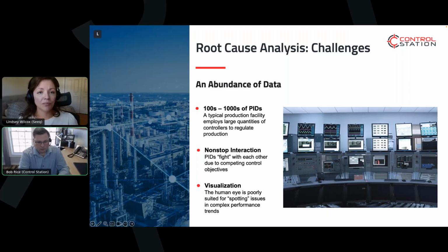Yeah, I think you're spot on. If all you have is process data, raw process variables, outputs, set points, modes, you're not getting the context to the data, and you're not actually getting what's going on, right? You have to have other tools interpret the data to say, hey, is this loop oscillating? Is it not? Does it have tuning issues? And then say, okay, show me things that are oscillating around this time, right? And be able to put context to what's going on and capsule-define, hey, this is the event. There was an event that happened here.